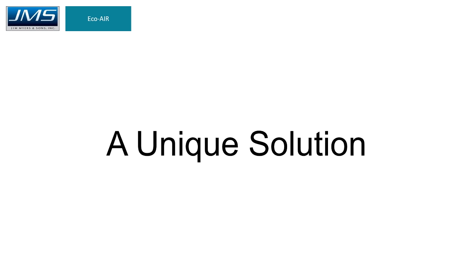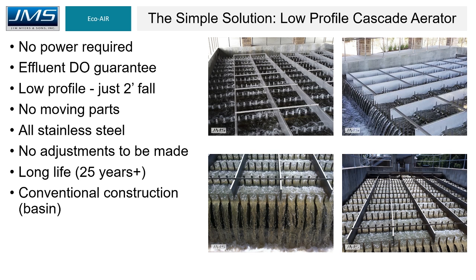A unique solution: the low profile cascade aerator, or LPCA, seen here. It has no power requirement, is static in nature, and we do guarantee a DO effluent. The low profile design requires just two feet of fall from beginning to end. There are no moving parts and it is constructed completely out of stainless steel. You can expect an extremely long life cycle — 25 years plus — and it is easy for contractors to install, simply inserted into a basin and bolted in.